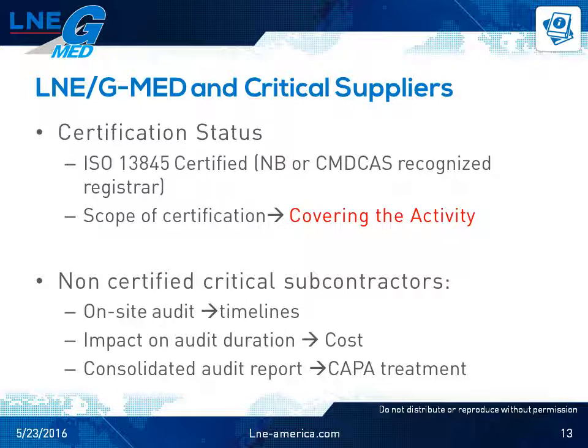Certification status. Now, should the subcontractor possess a valid QMS ISO 13485 certification, which covers the subcontracted activity and is issued by a notified body or CMDCAS registrar recognized by Health Canada in the framework of the CMDCAS program, an on-site audit may not be necessary. The evaluation of the subcontracted activity is conducted during the audit of the legal manufacturer, specifically while auditing the purchasing sub-process. However, the need for the on-site audit of the subcontractor may arise from the results of the audit of the legal manufacturer.